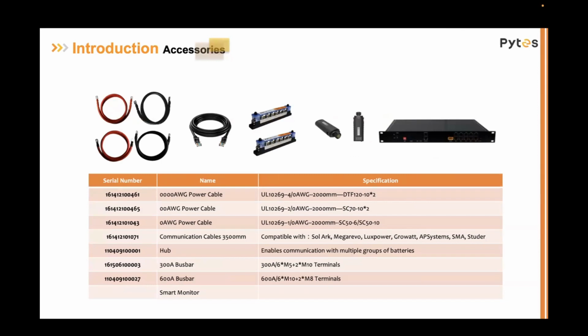These are some accessories that also come with the V5 that you can order extra. The hub is a great piece because it allows closed loop communication within multiple groups of batteries. We also have our battery combiner, where we hook up 300 amp and 600 amp rated battery combiners to connect these sets of batteries in parallel with the inverter system. We also have a home run communication cable, which runs from the master battery to the inverter interface, and home run cables to land these groups of batteries into the battery combiner as well.